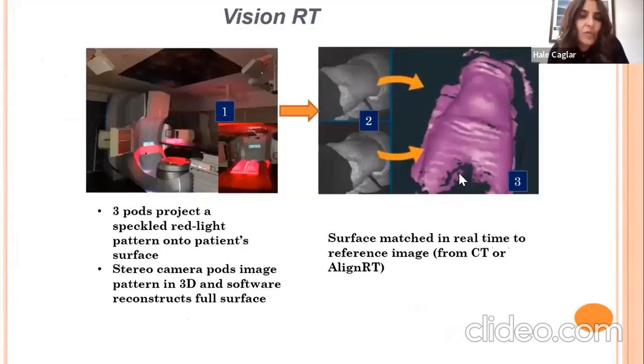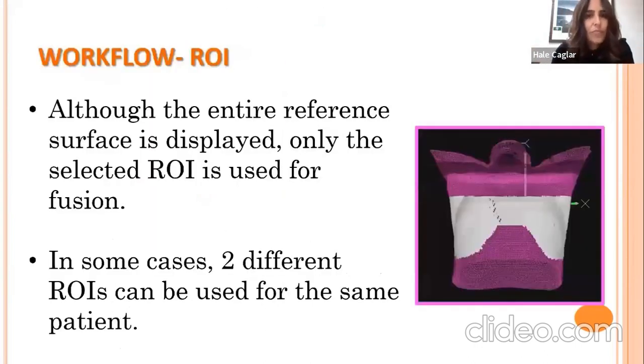The three pods project a speckled red light pattern onto the patient surface, the stereo camera pods image the pattern in 3D, and the software reconstructs the full surface. This surface is matched in real time to a reference image, which can come from the planning CT or from an AlignRT scan on the day of the fraction before setup. A region of interest (ROI) is then created — typically the area that does not move much but reflects the motion of the treatment field. In some cases, two different ROIs can be used for the same patient.